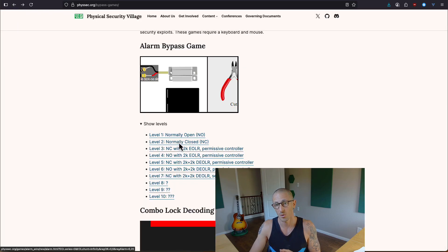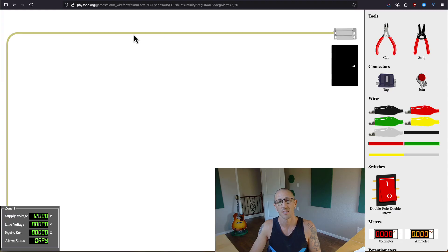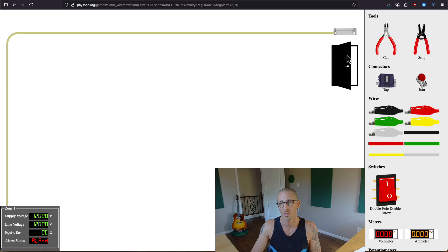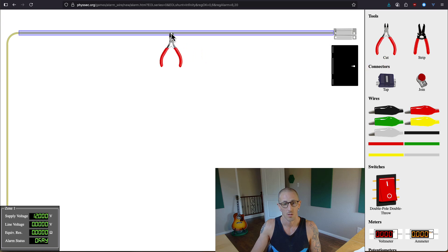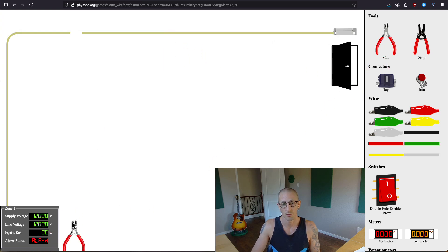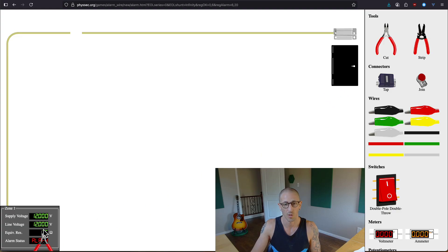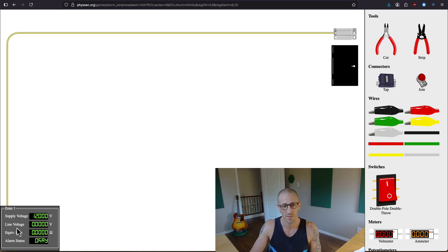Next up we have a normally closed circuit, which means there is current running through there. If we cut this wire, it's likely going to disrupt something the same as when we pull away the sensor. Right now we have an alarm state, and if we cut this wire the alarm goes off and opening the door also keeps it going. So we have 12 volts going through this line. Let me refresh the page — we can see a line voltage of zero and a supply voltage of 12.